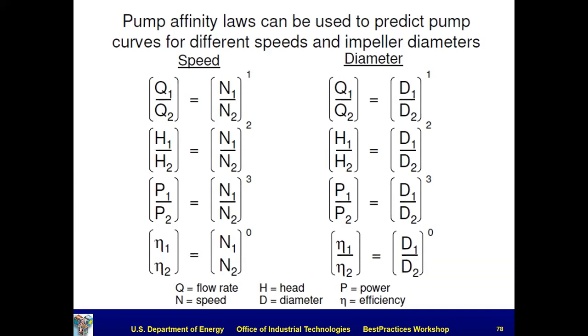These adjust the pump curve. This is what you need to know. Now, people use these things to predict operating points. And sometimes they get it close, and sometimes they screw the heck out of it because they don't understand that you have to take into consideration the system curve.